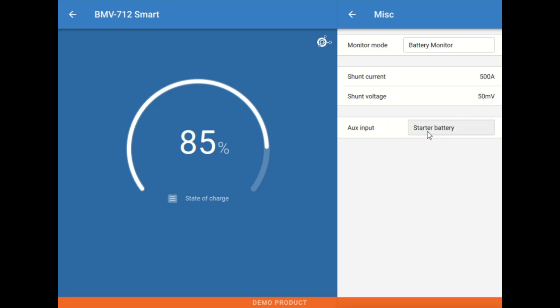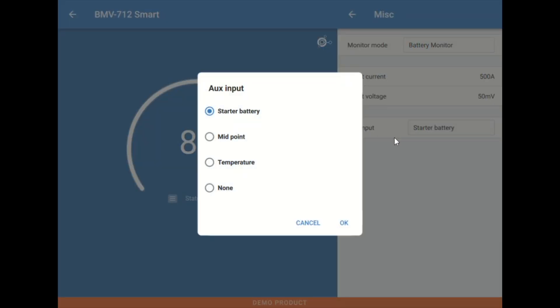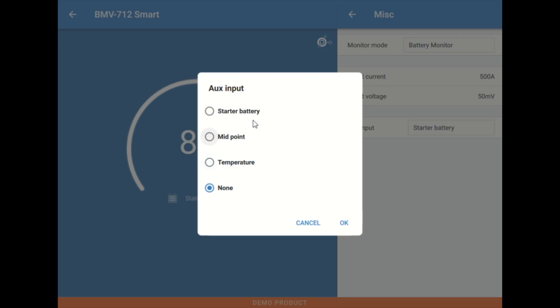The shunt voltage drop, which is almost always 50 millivolts. And then this bottom, this aux input is, what are the aux terminals on the shunt being used for? Are we just using it as normal? We can mark it as none. Do we have a temperature sensor or are we measuring a secondary voltage like a generator starter or a midpoint of the battery bank voltage?